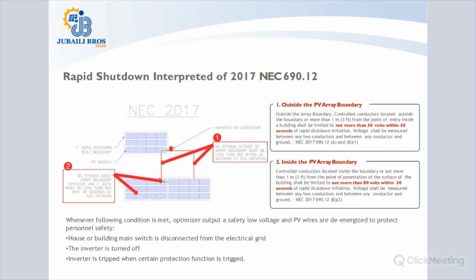So here they are saying that anywhere outside the PV array boundary, the maximum circuit voltage that should be in such a system is 30 volts within 30 seconds as you shut down the system. 30 volts within 30 seconds. If it's in a region inside the PV boundary, the maximum voltage expected there is 80 volts in 30 seconds.